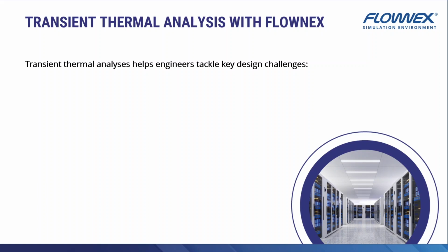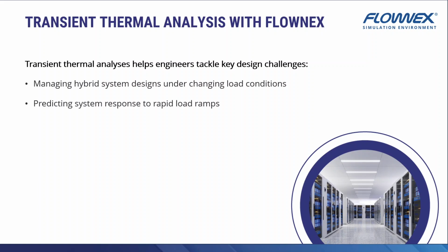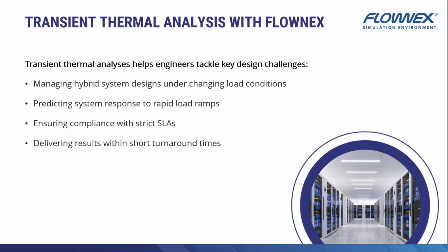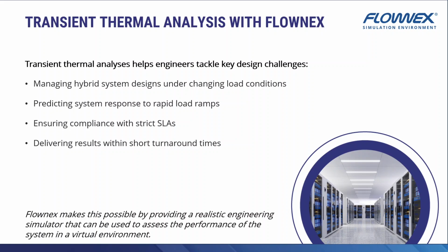Performing transient thermal analyses helps engineers solve several common design challenges. These include managing hybrid systems under changing load conditions, predicting system response to rapid load ramps, ensuring compliance with strict SLAs, and delivering results within short turnaround times. Flownex makes this possible by realistically modeling both the thermal and hydraulic behavior of all mechanical and control components in a modern data center cooling system. This creates an engineering simulator that can be used to assess the performance of the system in a virtual environment.